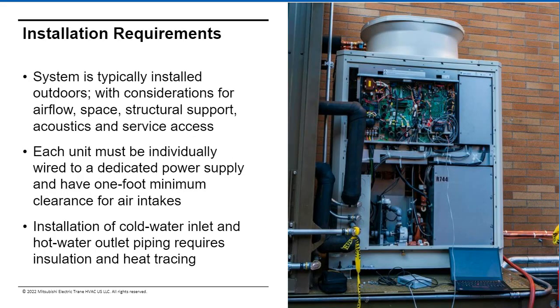The heat pump water heater should be installed outdoors at a minimum of 1 foot away from any adjacent building, according to most manufacturers. 3 foot in front is the required clearance on the front side of the unit that contains the high voltage electrical in and electrical disconnect per NEC, National Electric Code. For cold climate markets, the primary side of the heat pump water heater system should include food-grade propylene glycol to act as an inhibitor, but also to prevent against freezing, although heat tracing from the heat pump water heater to the inside of the building is also strongly recommended.